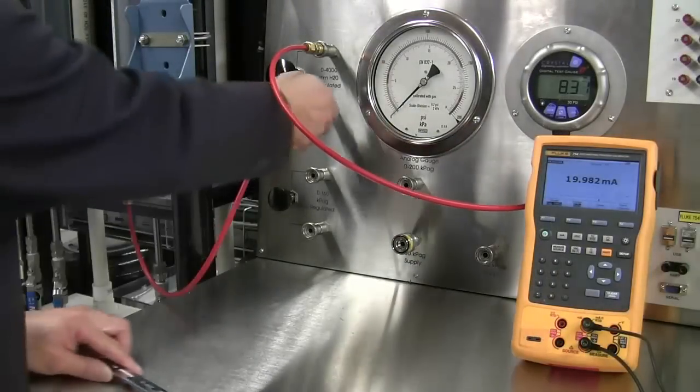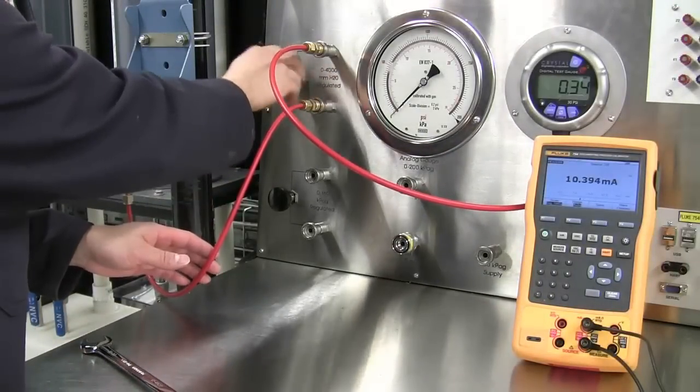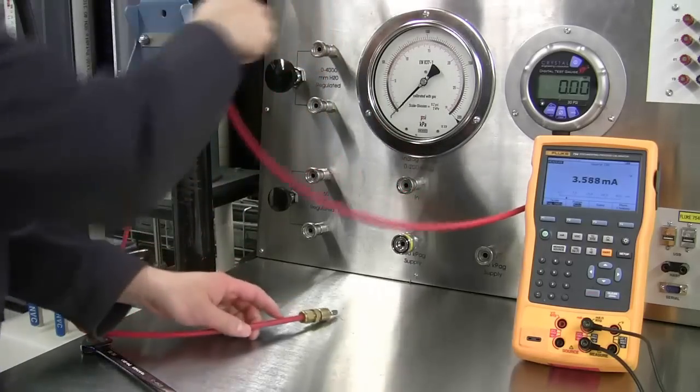When you are done calibrating the transmitter, back off the regulator until about 0 kPa and disconnect the hoses starting at the regulator end.